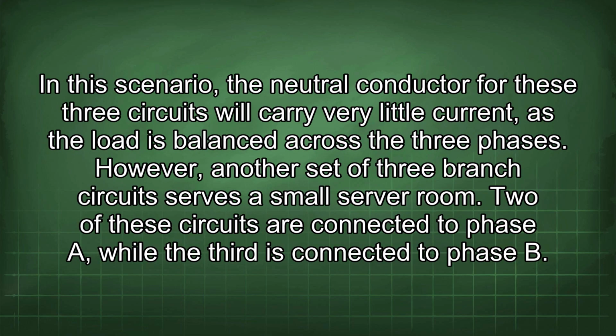In this scenario, the neutral conductor for these 3 circuits will carry very little current, as the load is balanced across the 3 phases.